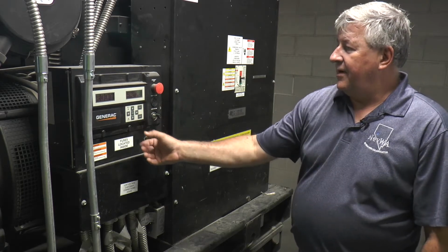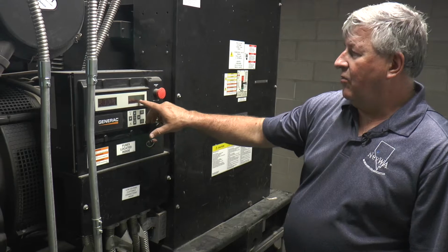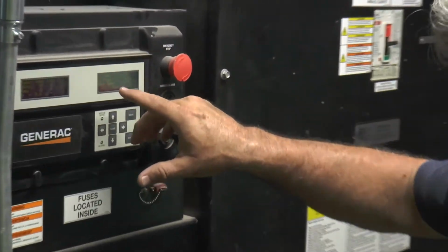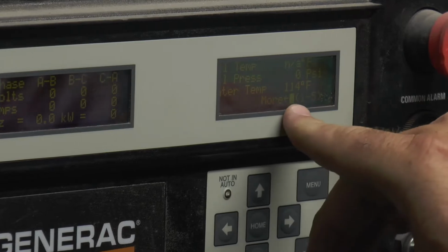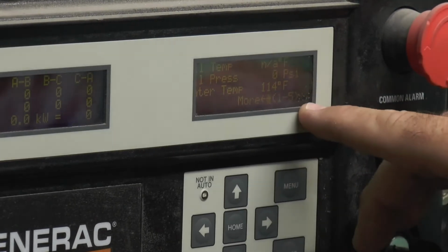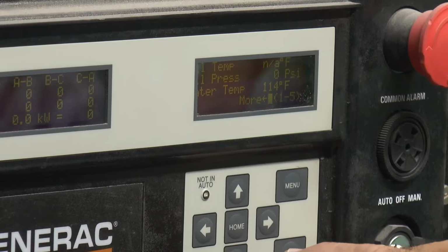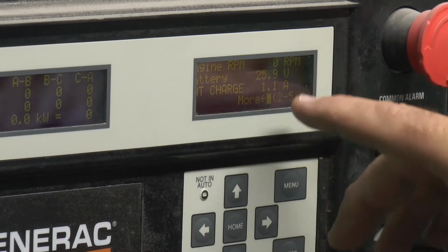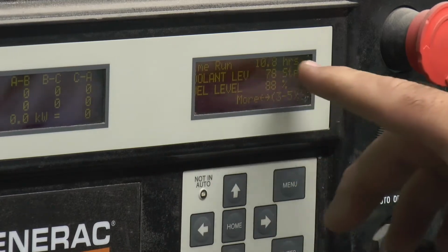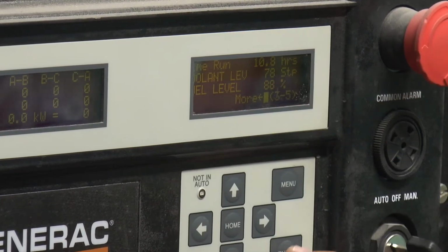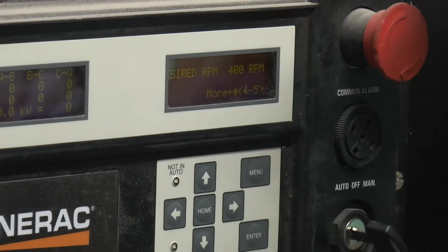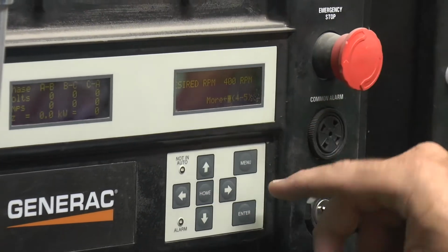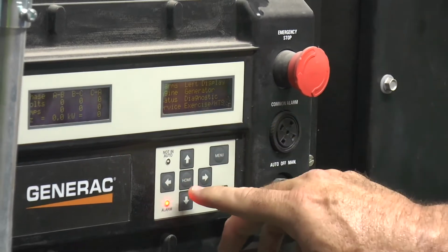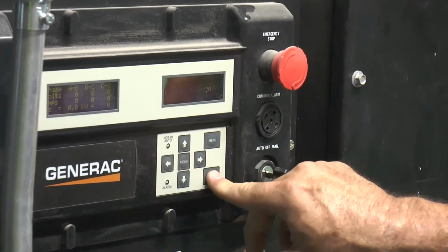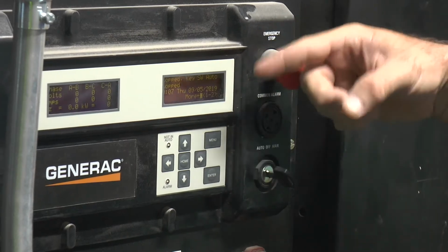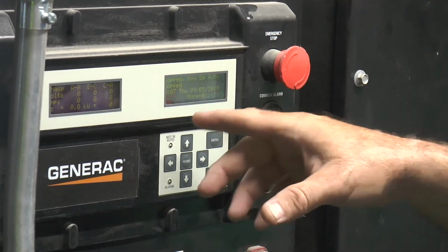engine. Press enter. You'll have oil pressure, water temp, and oil temp. You also have a display that says more left and more right. There are a total of 5 pages on this display. If you hit enter again, it'll go to the next page, which gives you battery charging voltage and amperage. Next is runtime, coolant level, and fuel level. And then RPMs for disengagement of the starter, things like that. The next would be status, which is basically telling us what condition the equipment is in right now. It's currently stopped, time and date.